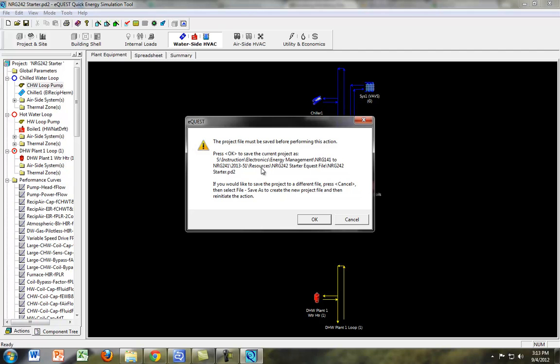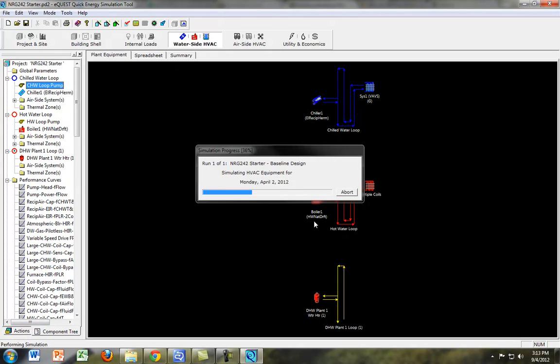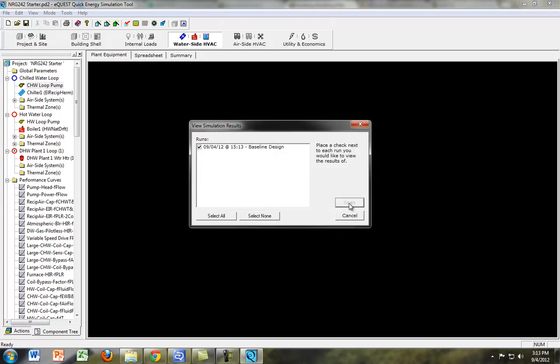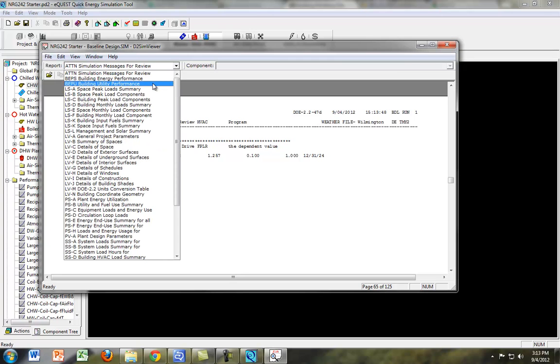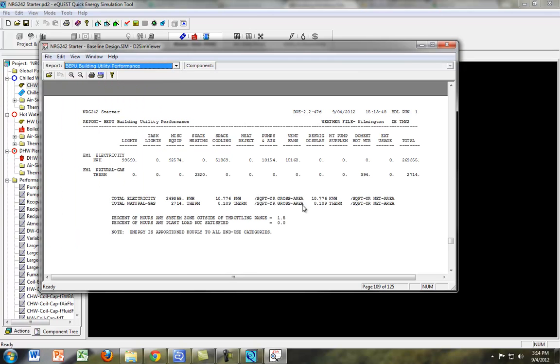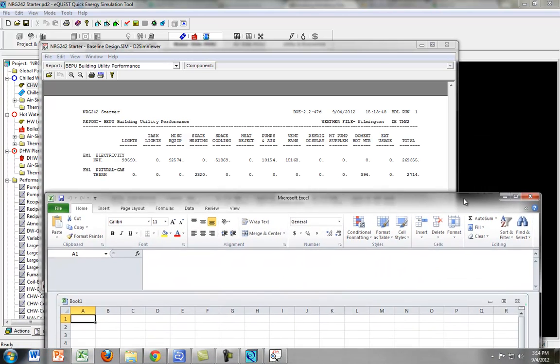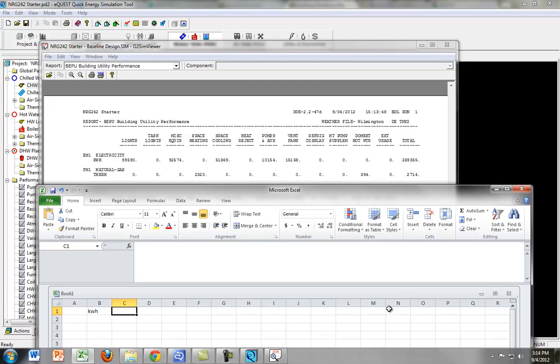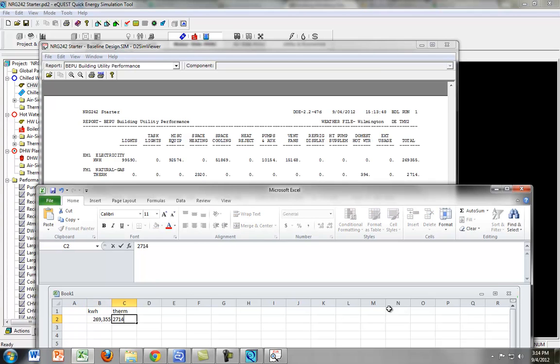So if you perform the simulation, and then view the detailed simulation output file, we want to see two things in here. First off, we want to go to the Building Utility Performance. And we're going to write those numbers down in Excel. So the first one is kilowatt hours and therms. There's 269,355 kilowatt hours and 2,714 therms.